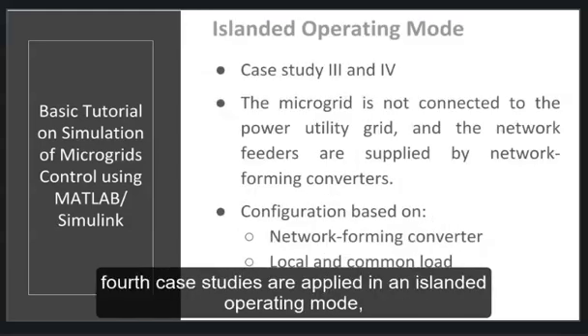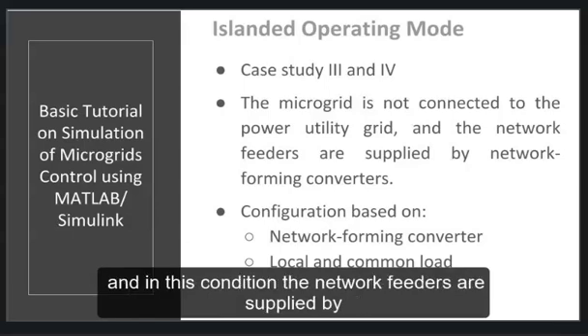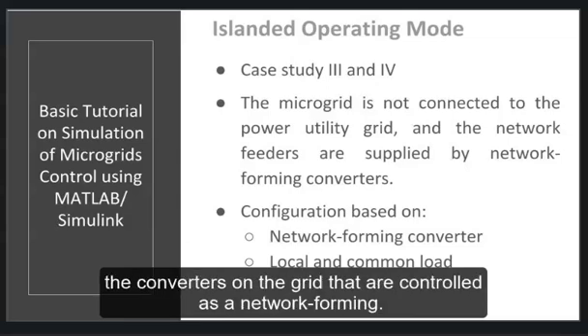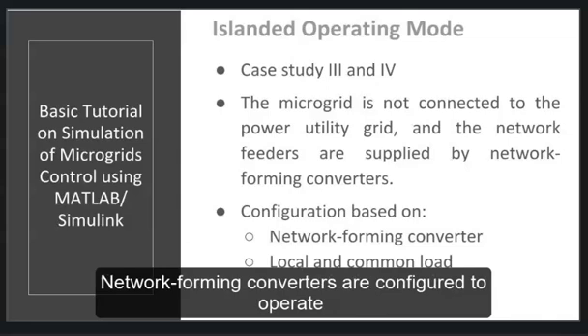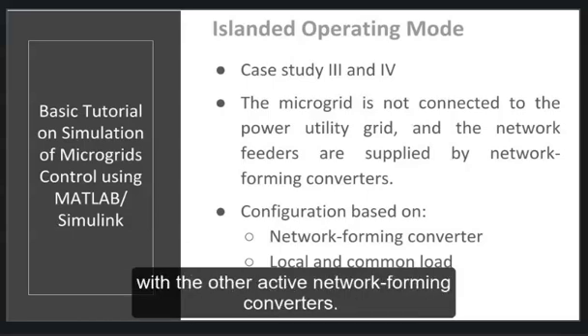The third and fourth case studies are applied in an islanded operating mode in which the microgrid is not connected to the power utility grid. In this condition, the network feeders are supplied by the converters on the grid that are controlled as network forming. Network forming converters are configured to operate equivalently as a voltage source and they are synchronized with the other active network forming converters.